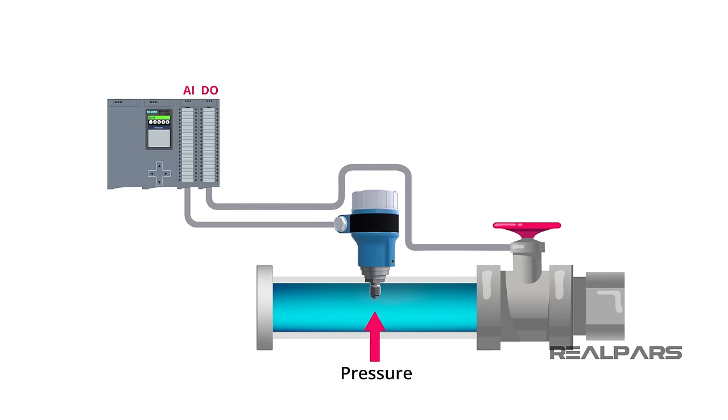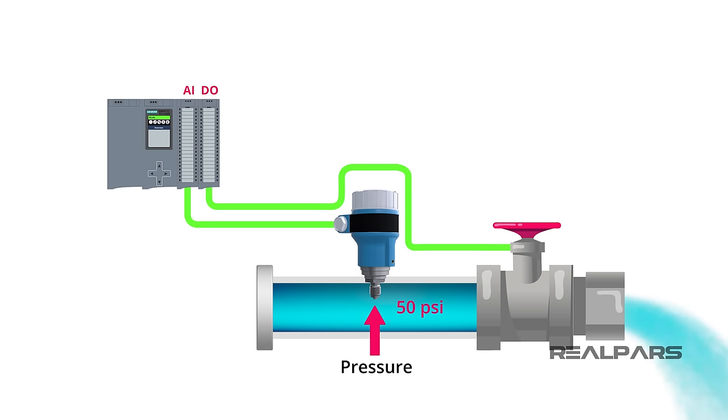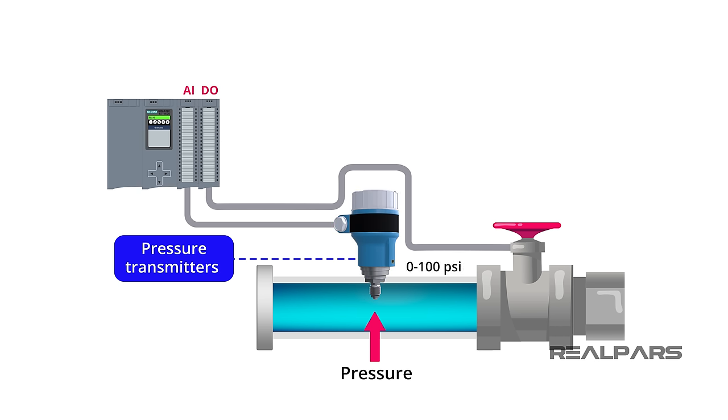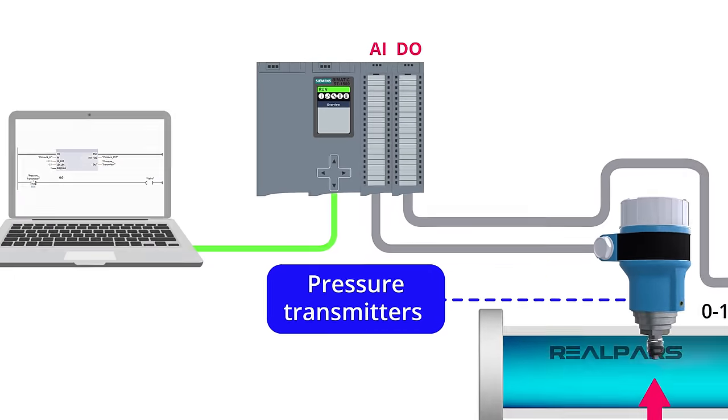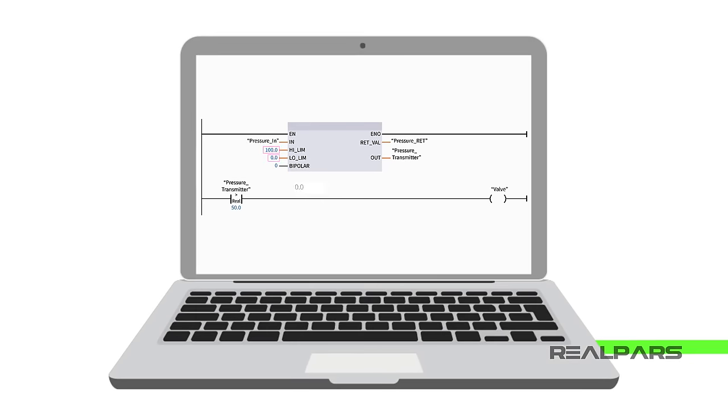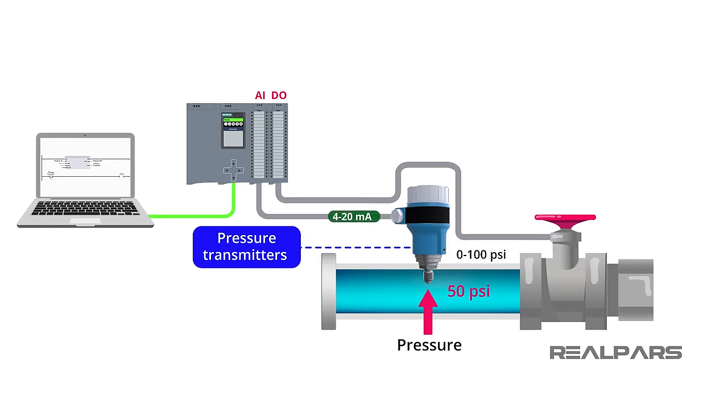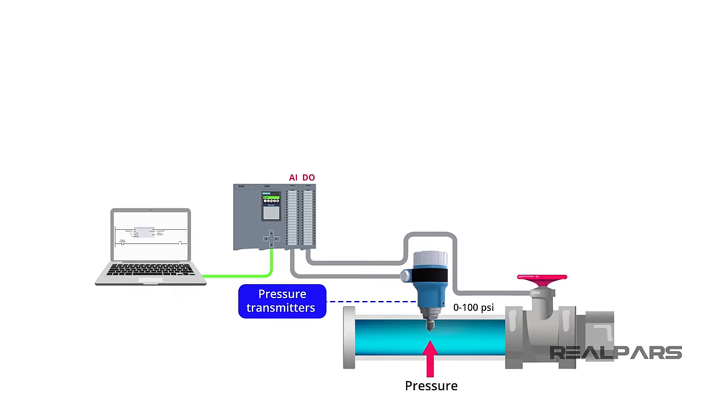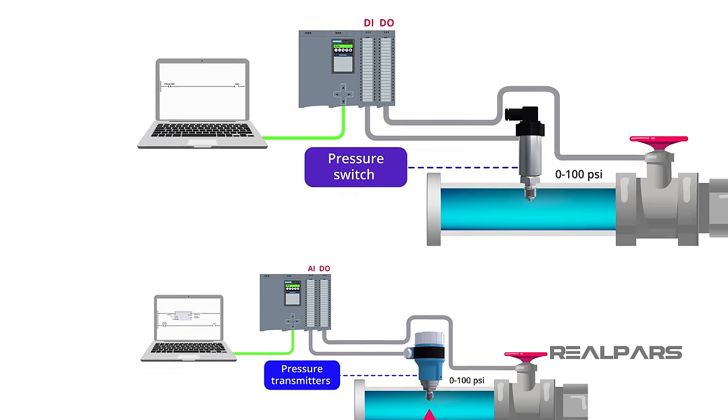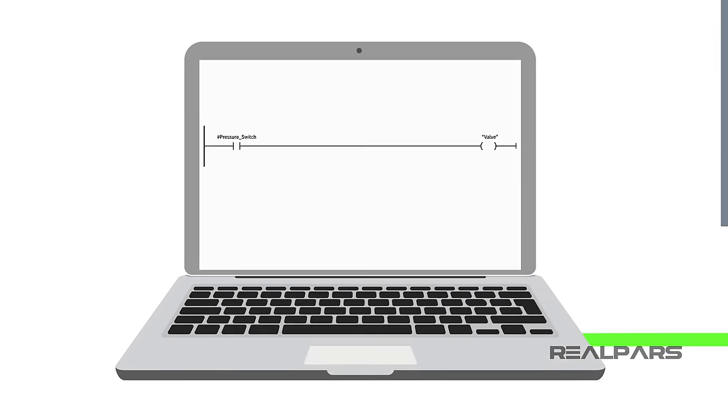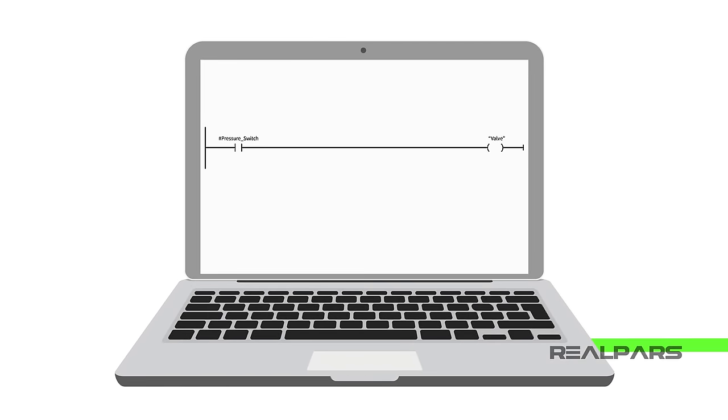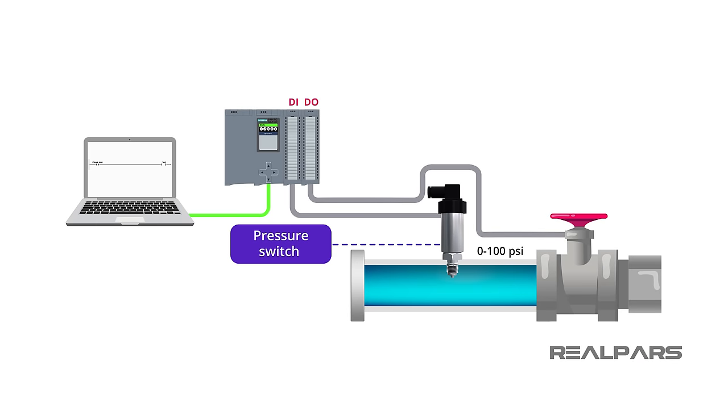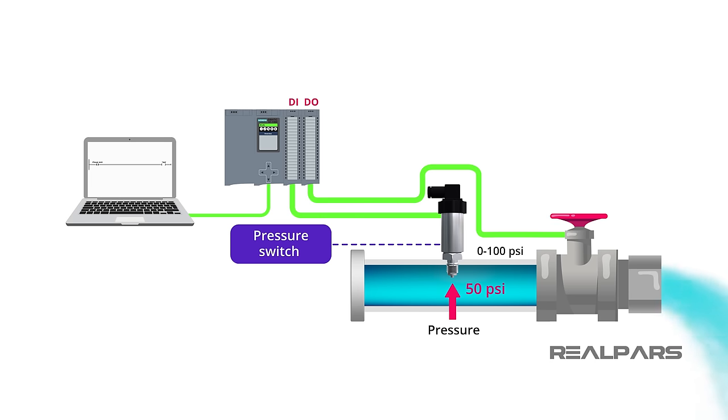Let's illustrate with an example. We have a process control system where we need to open a valve when the pressure in a pipe reaches 50 psi. We can use a Pressure Transmitter calibrated to produce a 4 to 20 milliamps output for a pressure range of 0 to 100 psi. We need an analog input module on our PLC, and we need to scale the analog module and insert code into the PLC program so that the 50 psi value triggers an event to open the valve. It's much easier to use a Pressure Switch connected to a simple PLC digital input module. The PLC valve control logic is much simpler as well. Bottom line, if you don't need to know the exact pressure and only need to know when a specific pressure point is dropped below or risen above a setpoint value, then stick with a Pressure Switch.